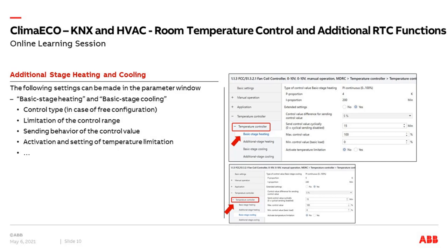Further adjustable parameters include the control type — for example, a fixed-value PI control with proportional band 4K and I-proportion 200. With free configuration selected, these are flexible and can be changed. There are further parameters such as the limitation of the control range so it's not running between 0 and 100% — you can limit this. There is also activation of temperature limitation, which we will cover in one of the next slides.